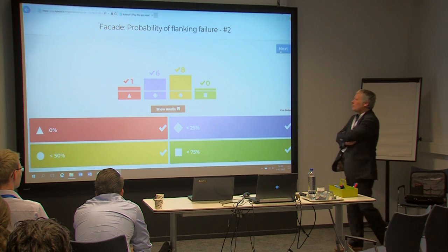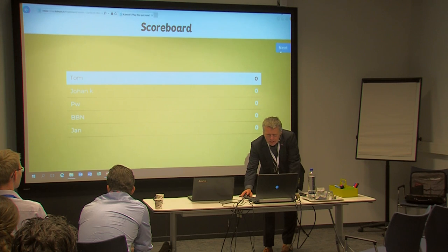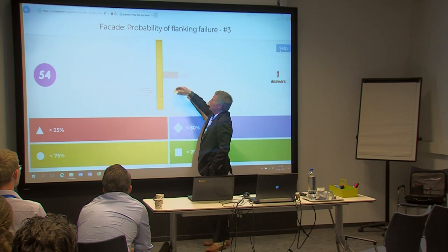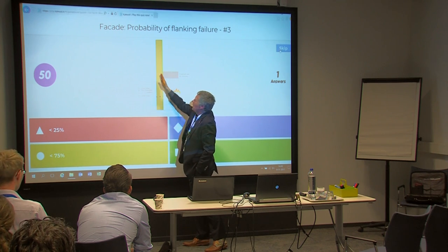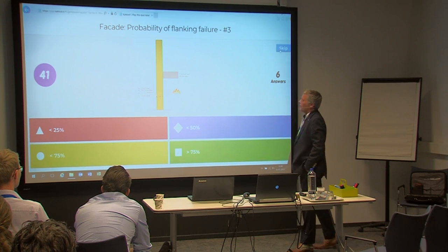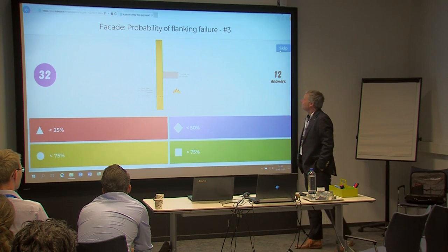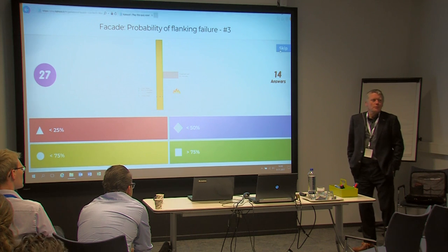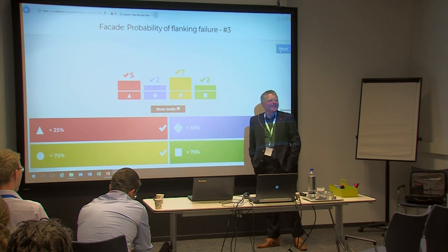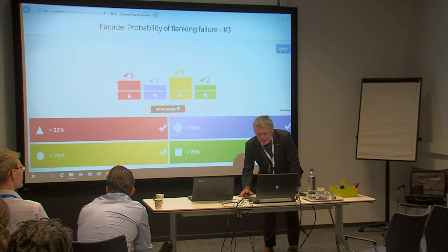The third facade detail: the facade runs along the compartment wall with no interruption, made entirely of non-combustible insulation with a steel cladding going through and non-combustible insulation in between. Results again show quite a large spread. Details showing large spread are the most interesting — they may need more thorough investigation.